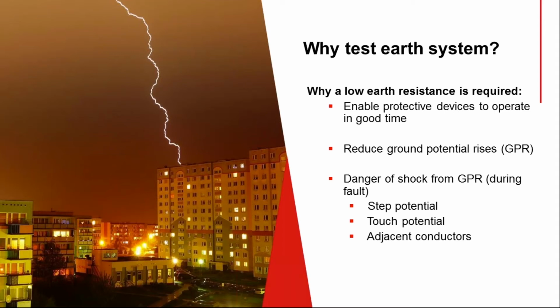Okay, so we kind of looked at why you want to do this. And these are some additional functions. You want to make sure that you have a good low ground so that your protective devices will clear properly. Some people will tell you, oh, well, the utility grounded neutral is doing that. Well, yeah, it is, but that's not the sole component. The grounding system is a parallel backup to that, and so it's a good idea to have your grounding system in place and operating well.